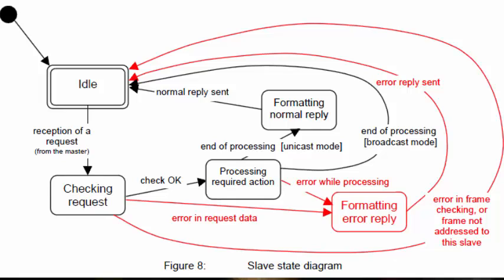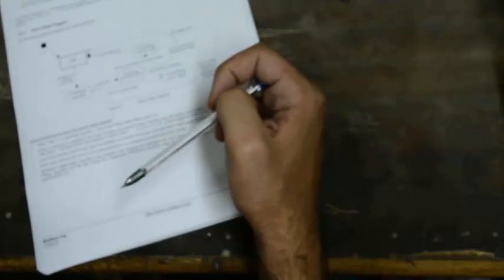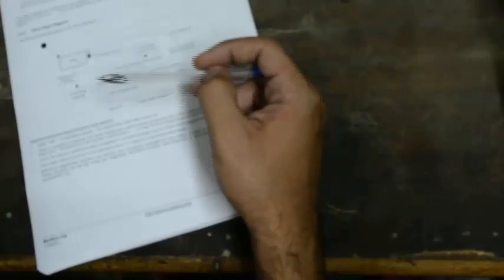If the slave discovers an error in the message — such as a framing error or a CRC error — it processes the error, stores the error state, and returns to idle. However, if the error is within the message content, for example if the master sent an unsupported request, the slave is allowed to respond with an exception response, informing the master that it cannot support the requested action.